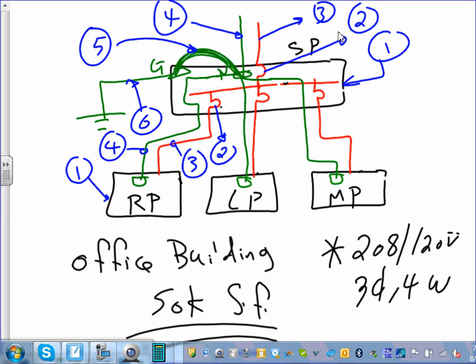Do you guys remember what we did last time? We had a service panel that's supposed to feed 3 panels, and we are to do a step-by-step load calculation for this service, right? So I'm going to walk you guys through what we have done. The building is a 50,000 square foot commercial building, powered with 208/120 3-phase 4-wire. We're bringing all these numbers that you're looking at. Can you see these numbers, 1 through 5 through 6? We need to size them. So later on, when you see size 1, these are the numbers I'm referring to. Let me go over it one more time.